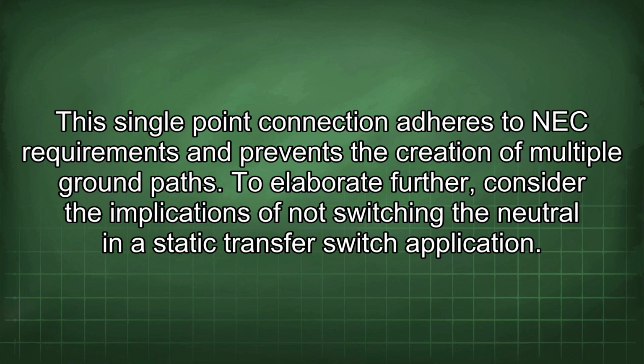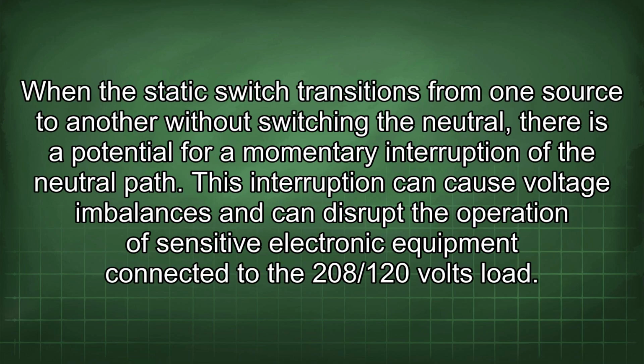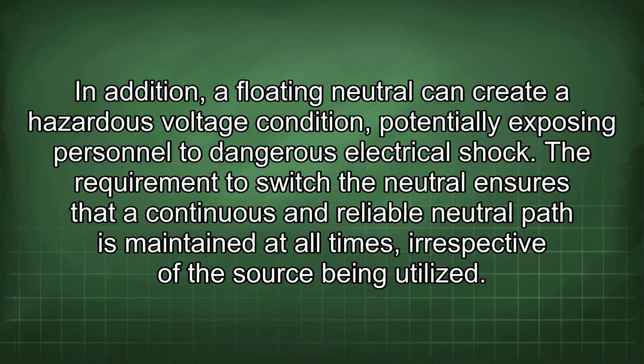To elaborate further, consider the implications of not switching the neutral in a static transfer switch application. When the static switch transitions from one source to another without switching the neutral, there is a potential for a momentary interruption of the neutral path. This interruption can cause voltage imbalances and can disrupt the operation of sensitive electronic equipment connected to the 208/120 volts load. In addition, a floating neutral can create a hazardous voltage condition, potentially exposing personnel to dangerous electrical shock. The requirement to switch the neutral ensures that a continuous and reliable neutral path is maintained at all times, irrespective of the source being utilized.